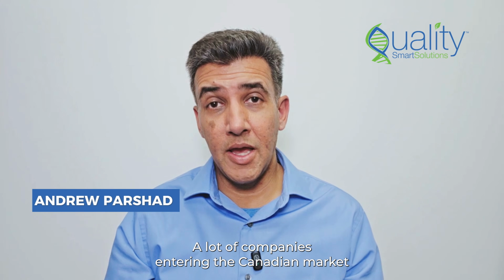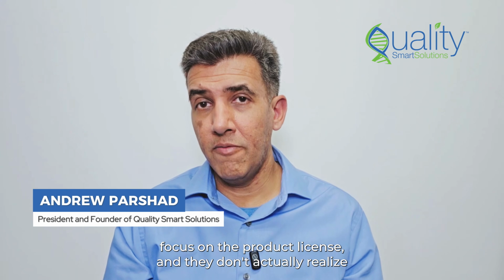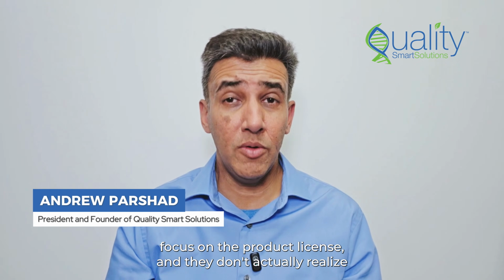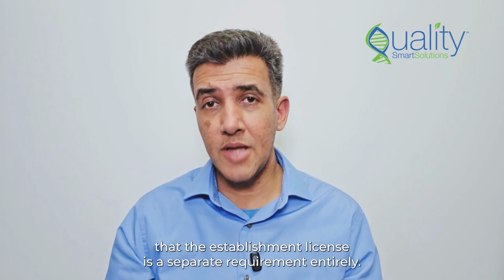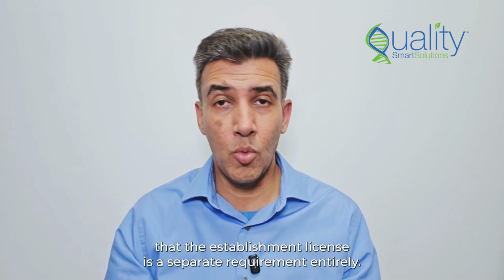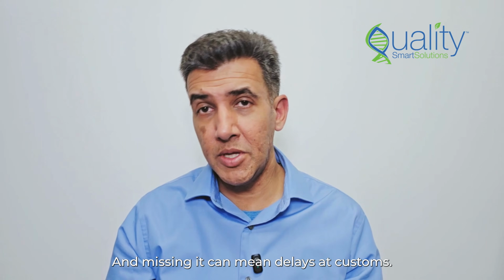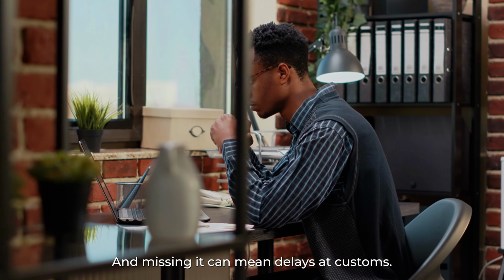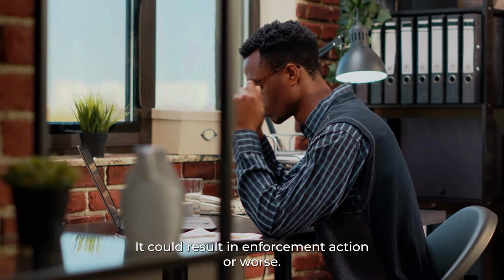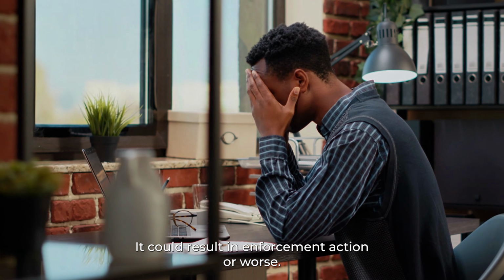A lot of companies entering the Canadian market focus on the product license, and they don't actually realize that the establishment license is a separate requirement entirely. And missing it can mean delays at customs, it could result in enforcement action, or worse.